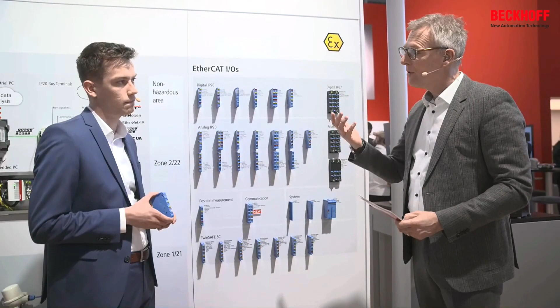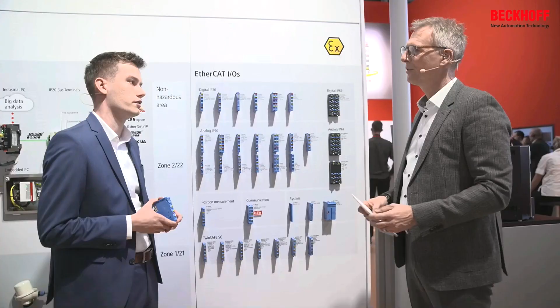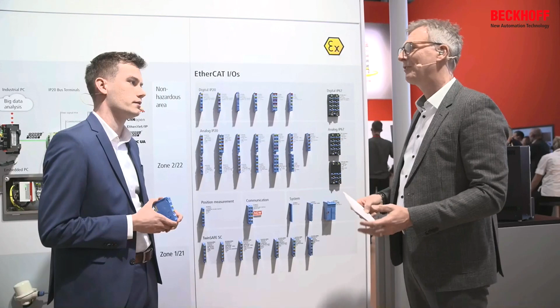Now, maybe finally, what is the reason for this approach? So why have we chosen that? The idea is that the customer wants to use the existing technologies like HART, like Foundation Fieldbus, or just single 4 to 20 milliamp signals. And we want to provide a solution to combine that with a new technology like Ethernet APL. So that's the idea. That's why we've chosen this solution and to integrate it into our existing system, of course.